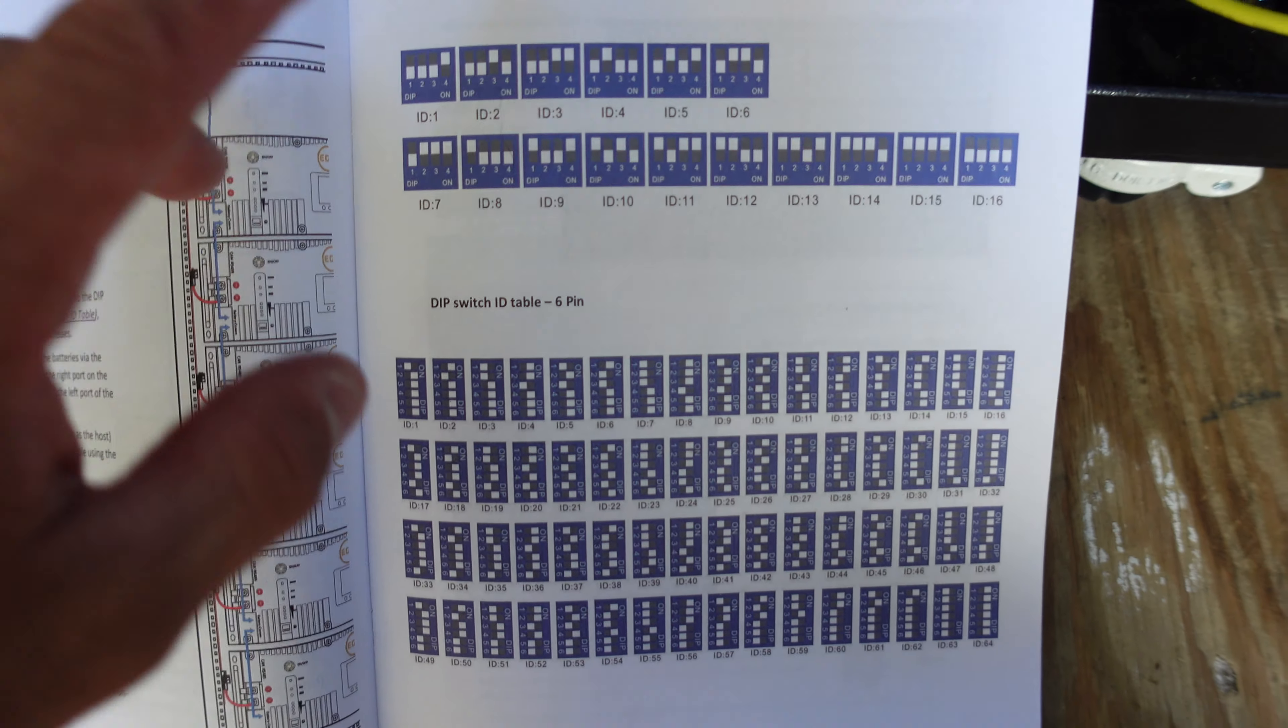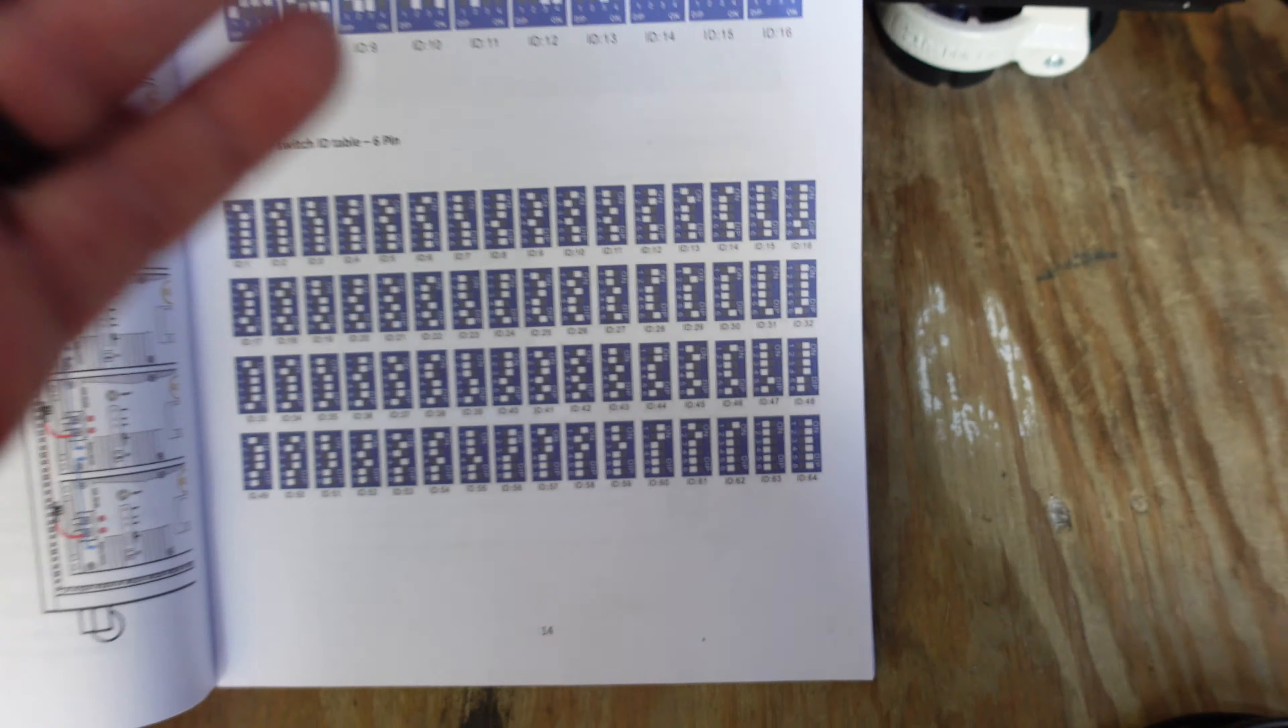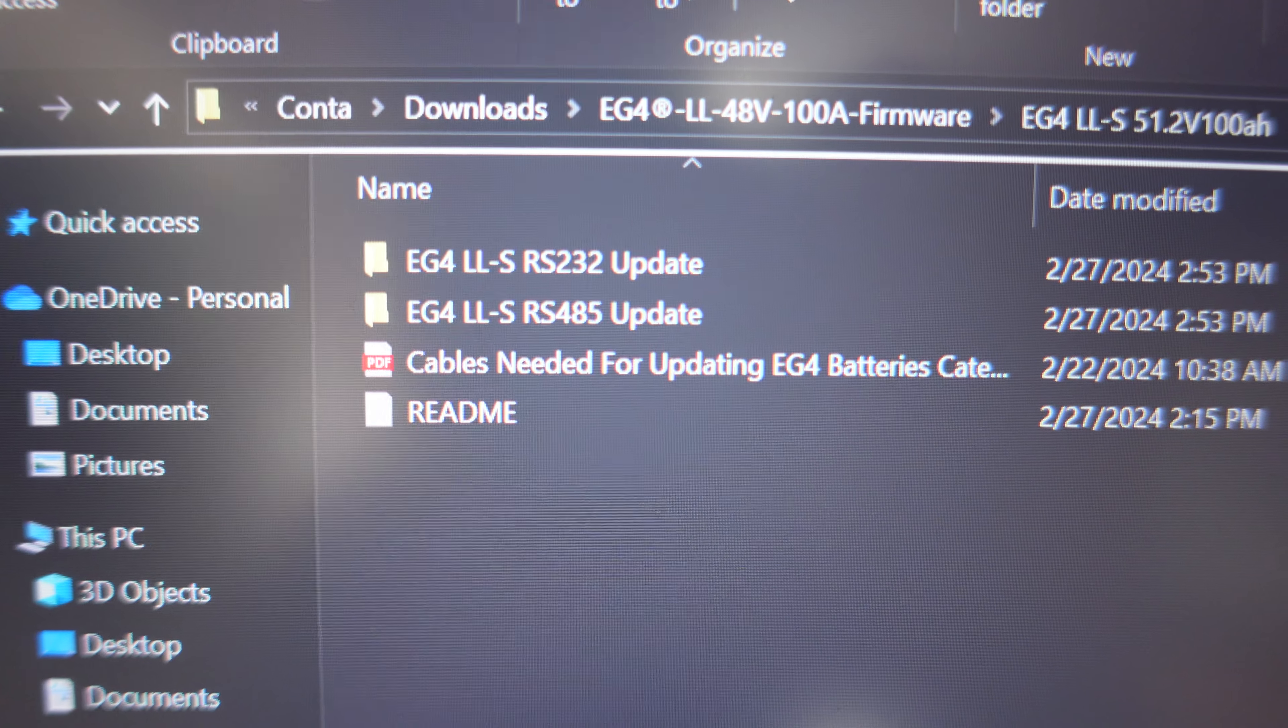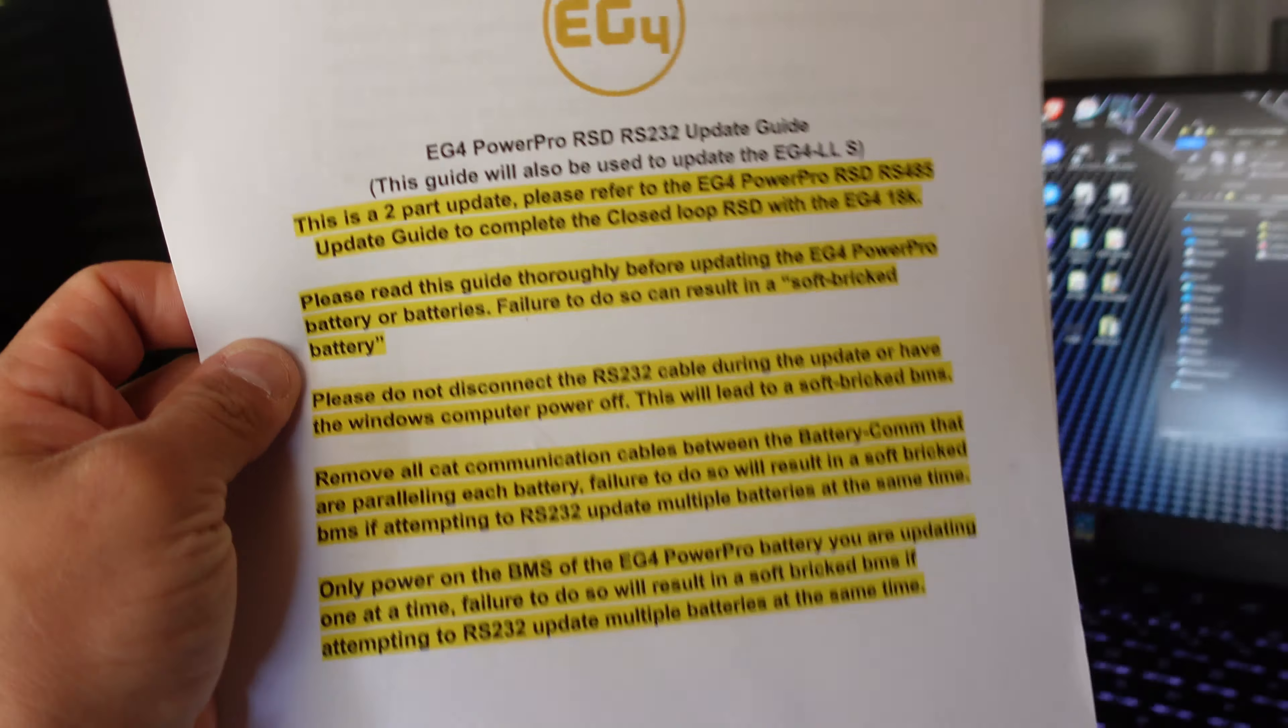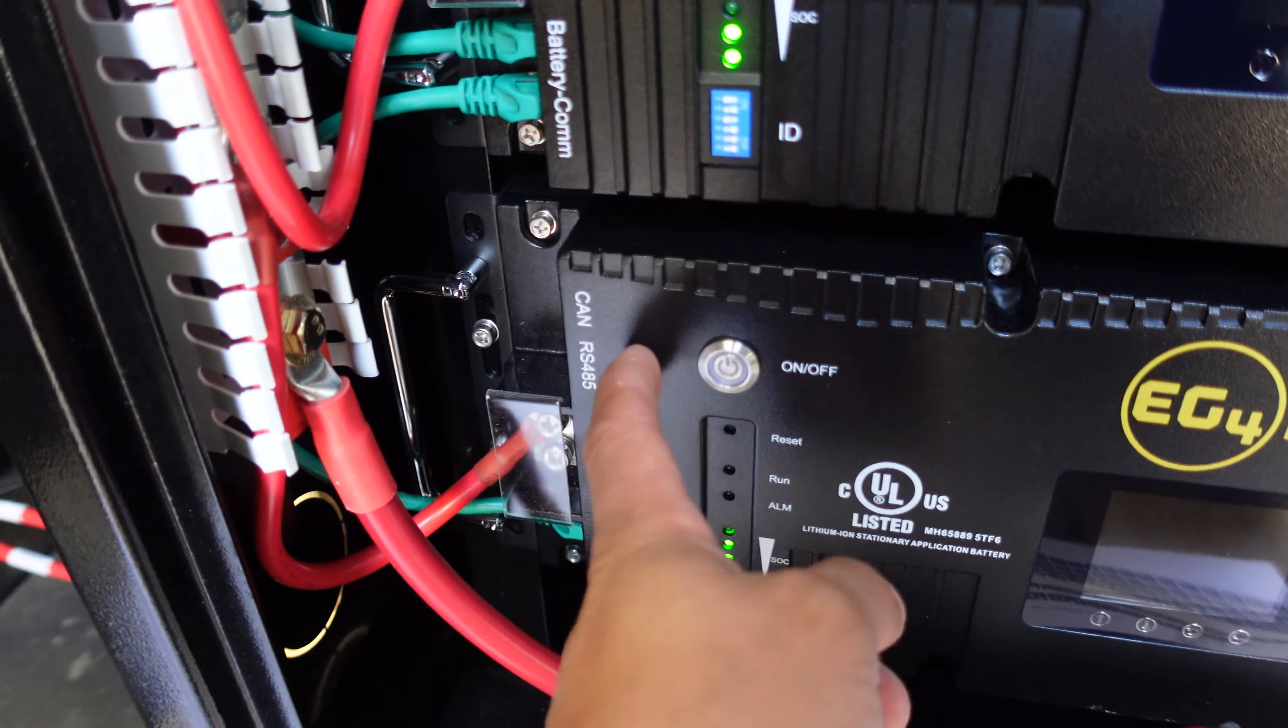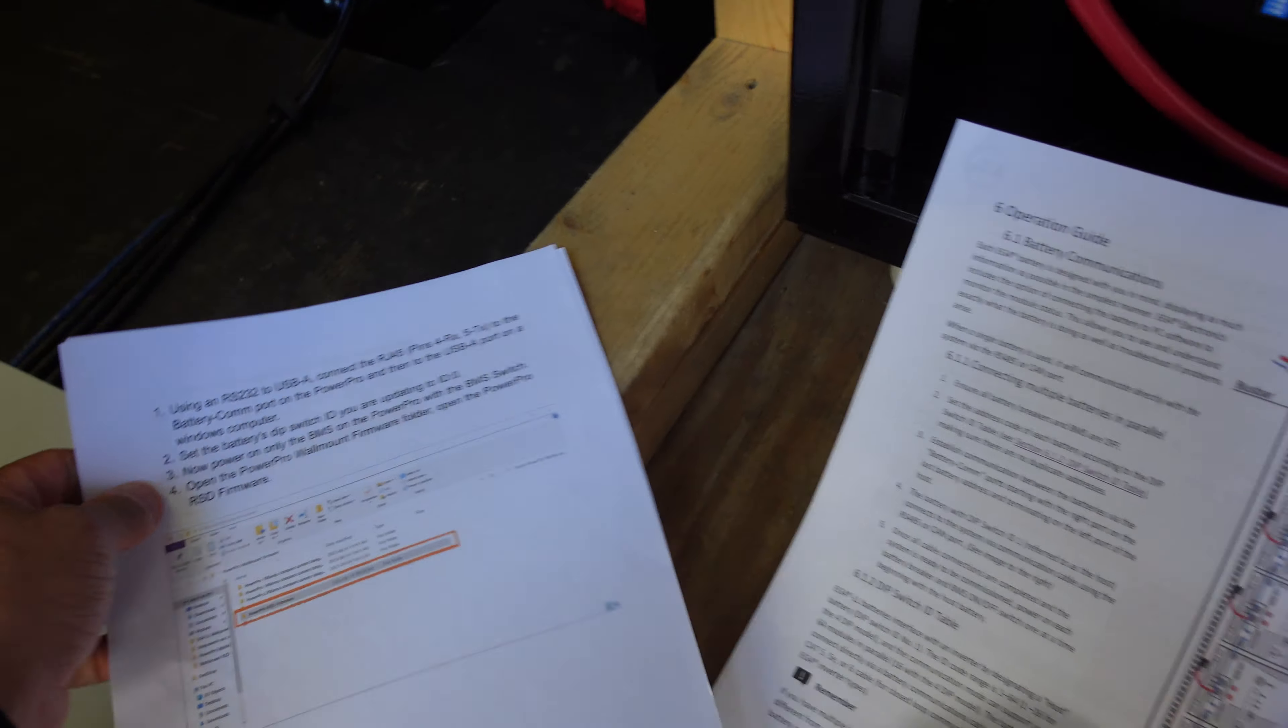I was talking to my rep, and looking at these switches, it goes 1 to 64. ID0 is actually 64, so all the switches need to go to the right. And then also in this file that I'm going to leave in that Google Doc for you guys, this has two things - the RS-485 is not the one you're following. Apparently we're going to follow the RS-232 update file, and that actually has this entire packet inside there. It does make a difference because the plug - this guy right here - where we need to plug it in is actually into the battery communications port instead of the RS-485 port.